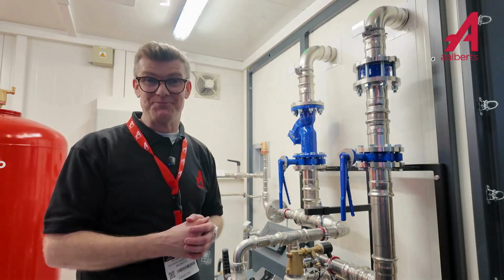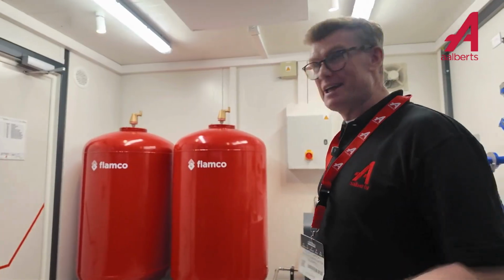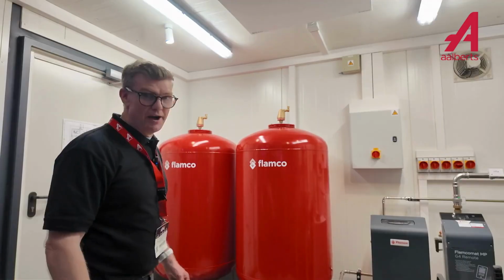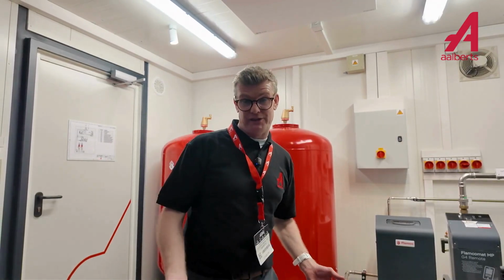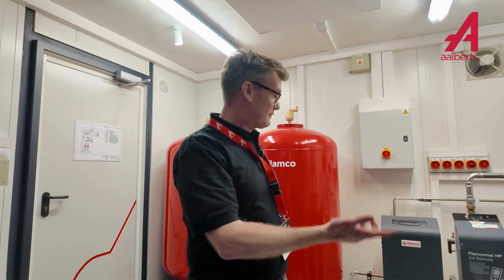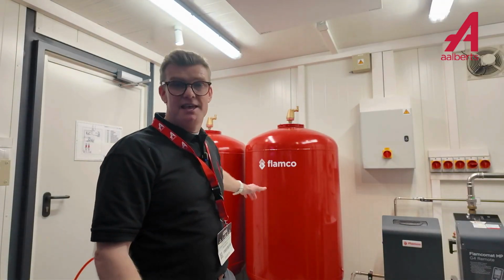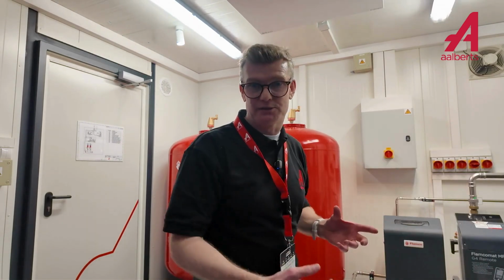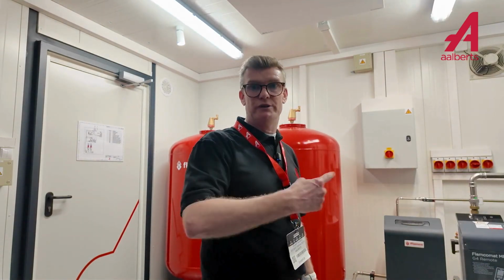I'm intrigued by these two big red things over here, you'll have to explain them to me. These two big red things are expansion vessels, part of our dynamic pressure maintenance solution. In the UK we call it spill and fill. In short, when the system pressure increases, we spill the excess volume from the system into the expansion tanks. Then when the system contracts, we fill back the system, utilizing that expanded volume to replenish the pressure within the main system. That's where we get the spill and fill technology from.